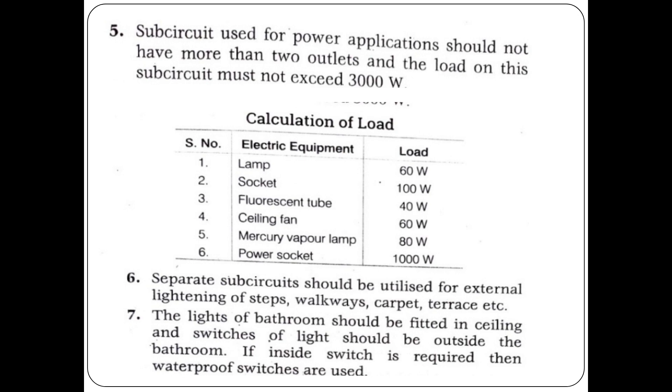A sub-circuit used for power applications should not have more than 2 outlets, and the load on this sub-circuit must not exceed 3000W.